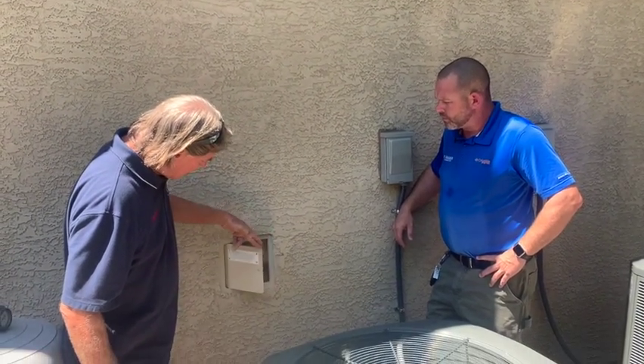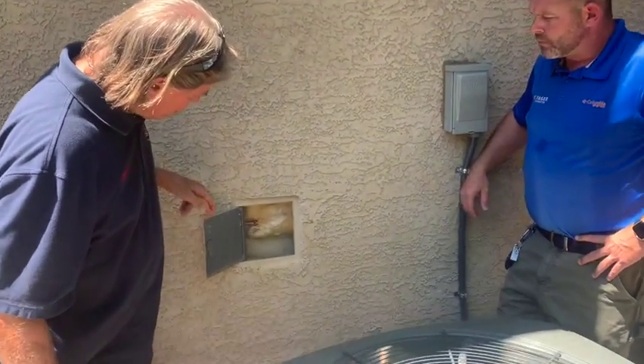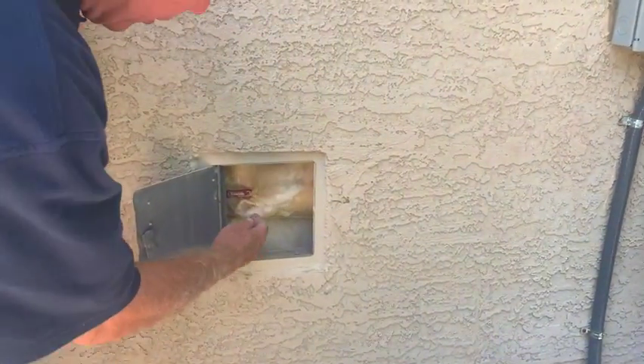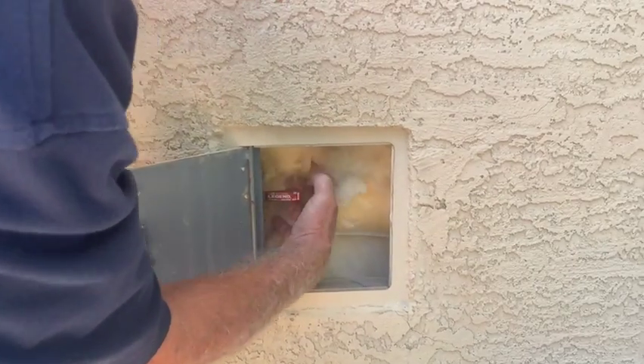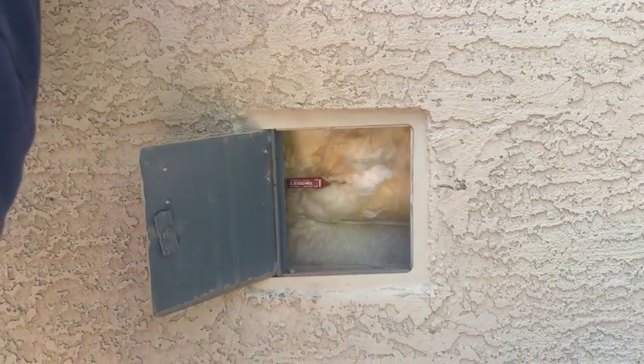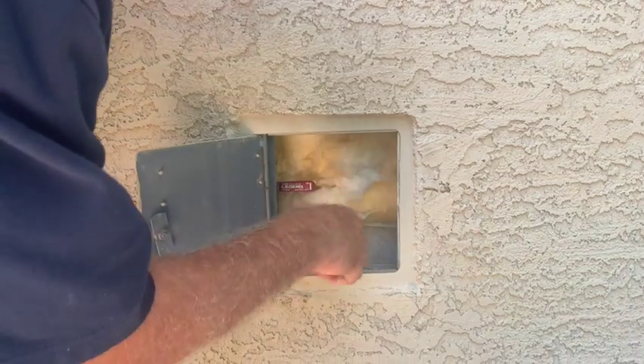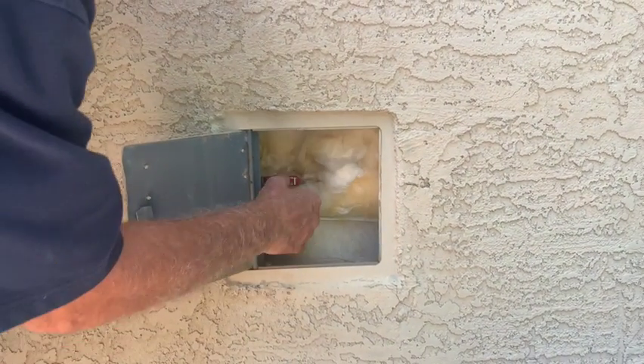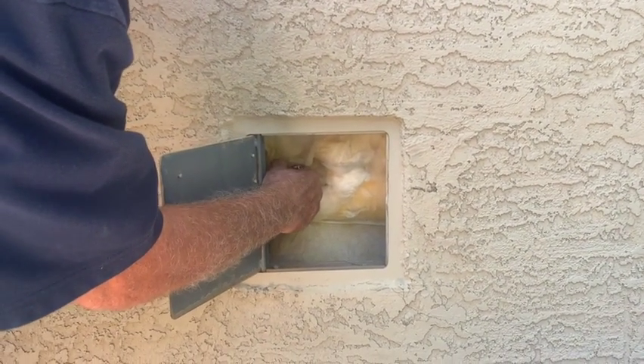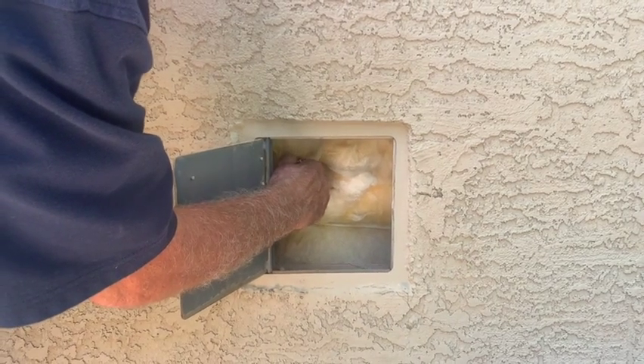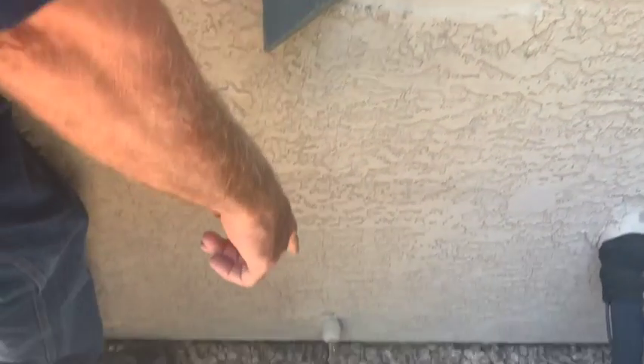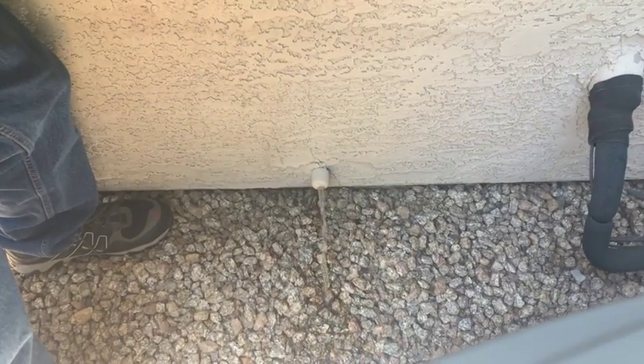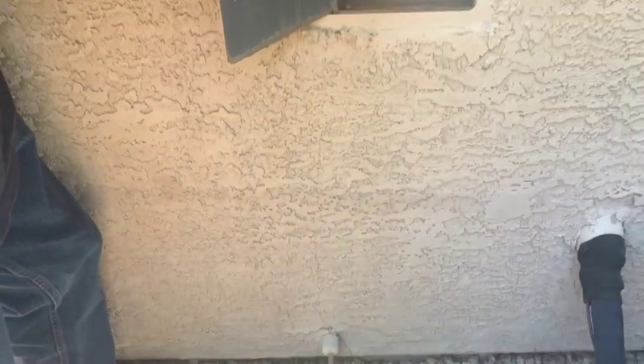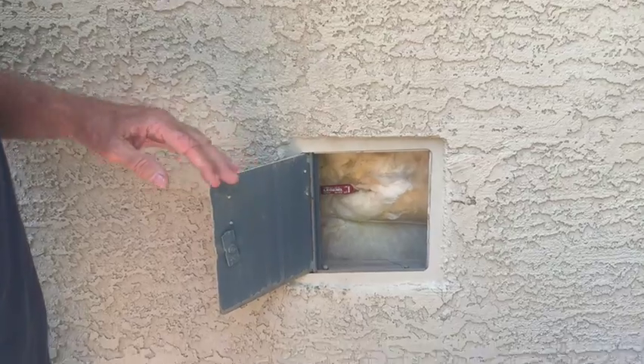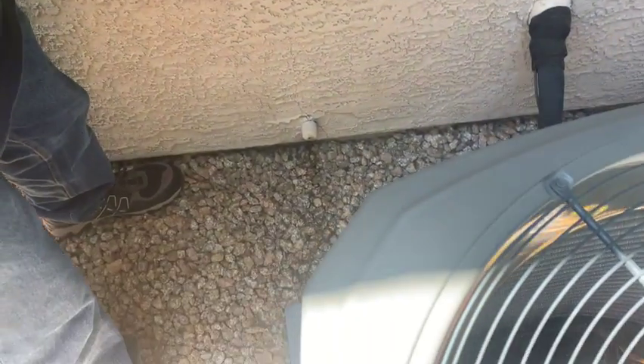This one is placed behind an access panel, which is fine. And then this is the actual valve handle that you see. So the homeowner is probably going to want to put on a glove or something so they don't get insulation on themselves. And then they're going to operate this valve. When they operate this valve, water is going to be flowing out of this orifice right there. I'm not going to flow it at full flow because this one is set up right by this air conditioner. It's just going to blast water all over us.